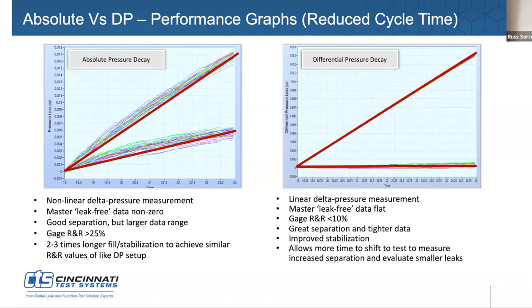Now, does that affect when you add that volume? Is it going to negatively affect the cycle time because now you have to fill up both volumes? Is that a factor? No, that's usually not a factor unless it's a really large volume. Well, I'll say yes, it could be, based on size of the part, size of the reference volume. So there's no special answer that's one way or the other for that one. Lots of these are application driven discussions and formulations for testing the part accurately.